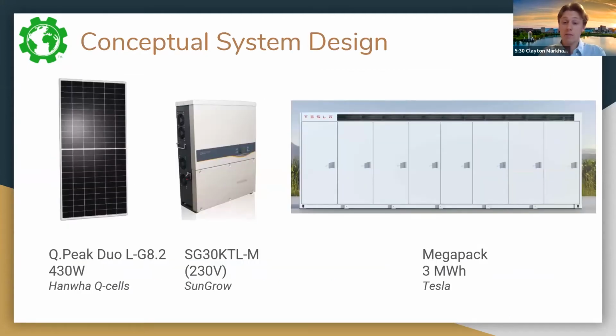Now we'd like to go into some details of our deliverable sections, starting with the conceptual system design. These are our 3 equipment specifications for panel, inverter, and battery pack. We chose the QPeak Duo 430 watt panel for its high efficiency and power rating, and a 30 kilowatt, 230 volt inverter from SunGrow. Because it has such high power and 2 maximum power point trackers, we were able to minimize the number of inverters needed.